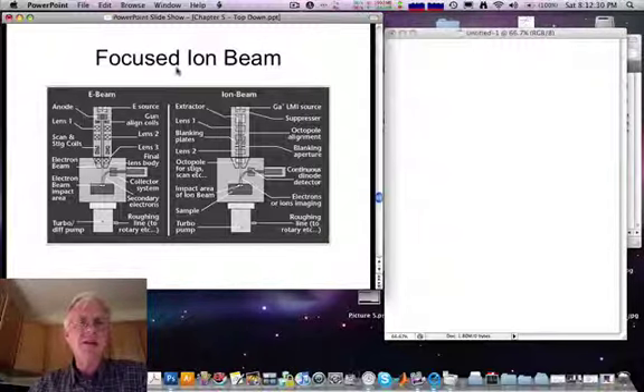So by using lenses which tend to be electrostatic rather than magnetic in a focused ion beam, because of the difference in the charge to mass ratio of an ion versus an electron, one can bring a beam down to a sharp focal point on a sample. Because of the increased momentum of ions in the ion beam compared with electrons in the electron beam, atoms will be knocked out of the surface of the material being bombarded. In fact, these are very versatile systems and can come equipped with lines for reactive gases that, either by writing with electrons or ions, can let you deposit metal or carbon films, for example.